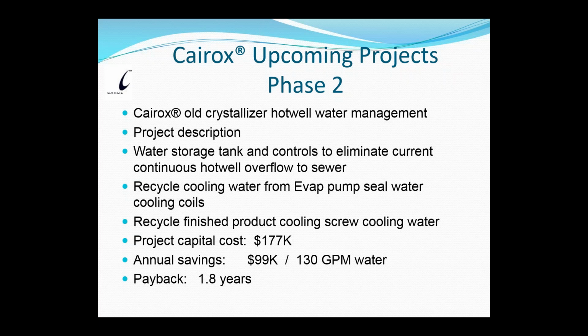Now, for the other part of the process, that hot well water runs around 83 or 84 degrees Fahrenheit. Our raw water coming in runs at about 64 degrees Fahrenheit. The interesting thing about using recycled water now is we've improved the performance of our RO system, because the warmer temperature actually allows the membranes to work better. Another side benefit is that all the piping in the boiler house, which used to rain water down on humid days from all the condensation, doesn't do that anymore either.